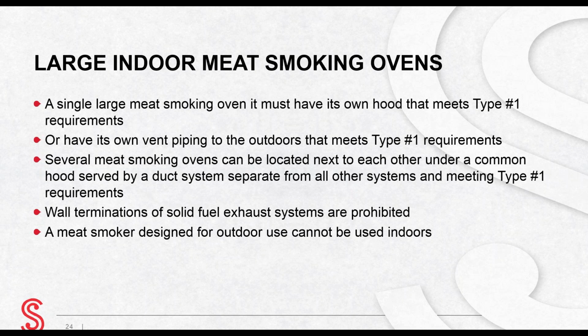Wall terminations of solid fuel exhaust systems are prohibited. No ductwork through walls is permitted, only to the roof. A large meat smoker designed for outdoor use cannot be placed indoors, regardless of the vent piping used.